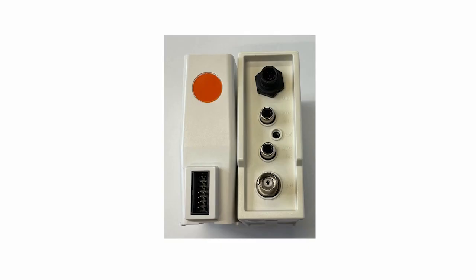Moving on, there is an orange module for measuring pH ion. At the top of the module, there's a socket to connect the digital electrode, and below that, a cinch socket to connect the external temperature probe. A small input for the reference electrode can be found below that. The last two sockets are the cinch and BNC ones used to connect the multi-pin or S7 cable.